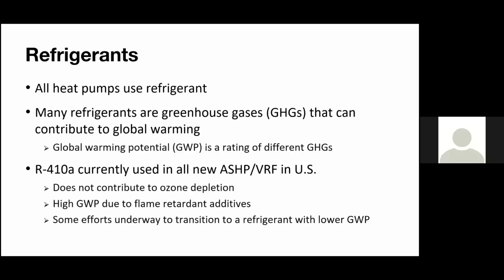There are things happening with the alternatives that are available out there called A2L refrigerants, and putting those in buildings and systems, which we're waiting on the building codes to accept. So there are things on their way, but right now there are no phase outs on refrigerants like R410A. There have, however, been some phase down rulings that came out recently from the EPA, or the Environmental Protection Agency, which we expect to open up a large market for recycled refrigerants in the future.